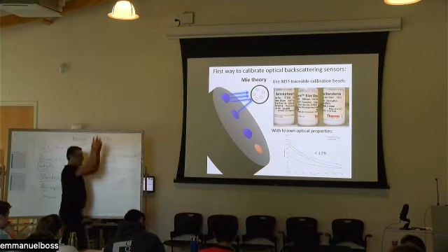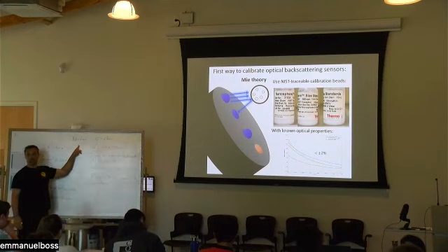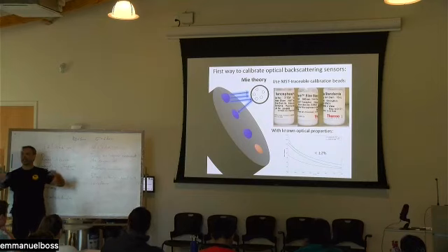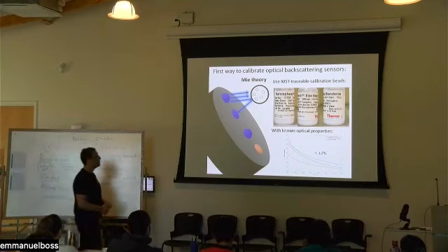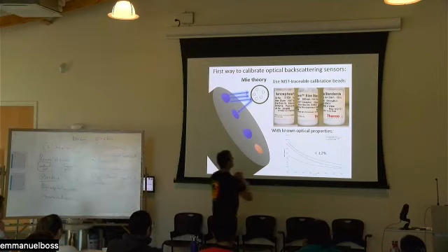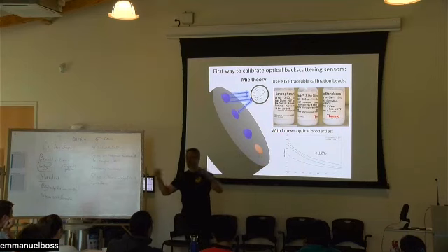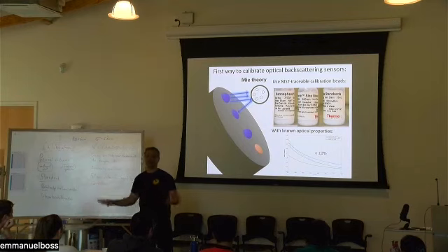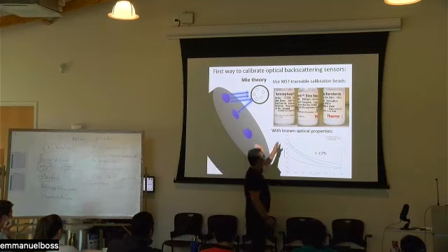Nanometer. That's the standard deviation around that mean, which has its own uncertainty. And we have 6% uncertainty in the exact position. And then on top of it, there's a tail that you can go on both sides. This is from the manufacturer and it's disclosed. You have a log number, which is really important because this is how you go back. If there was a problem, you tell people, look, everybody should stop using that log. There's been a problem with calibrating. That's where traceability comes in.